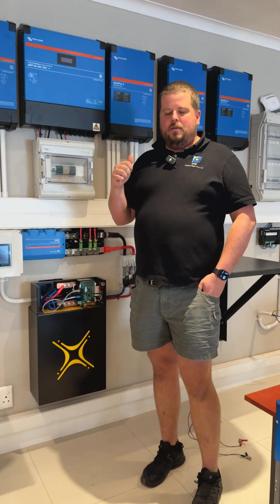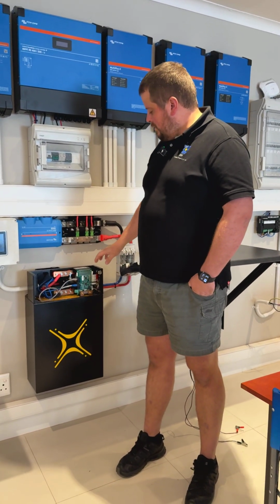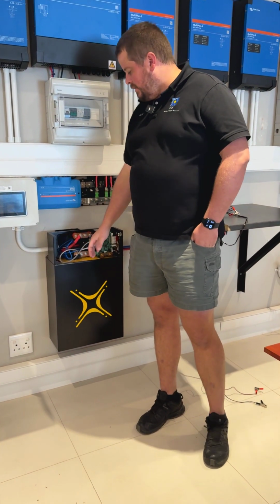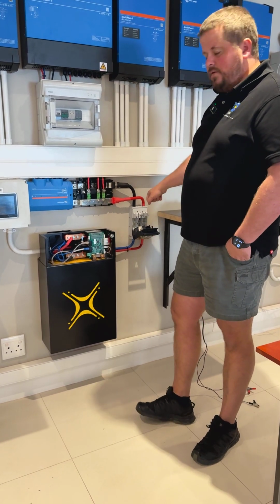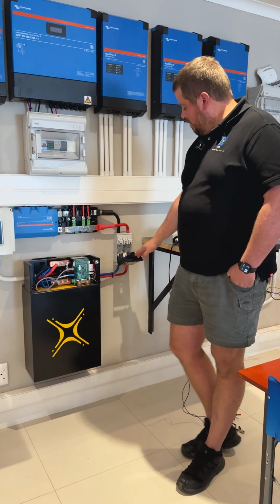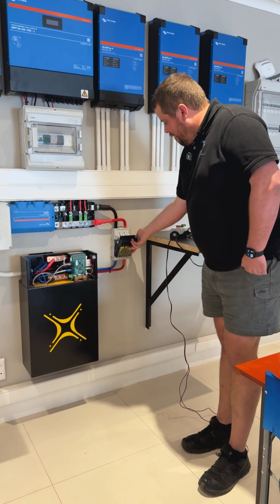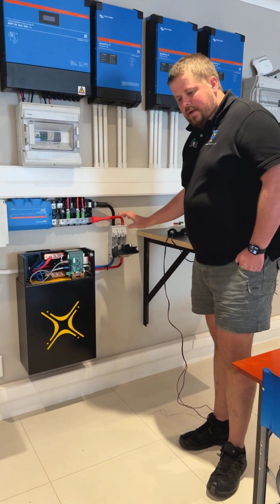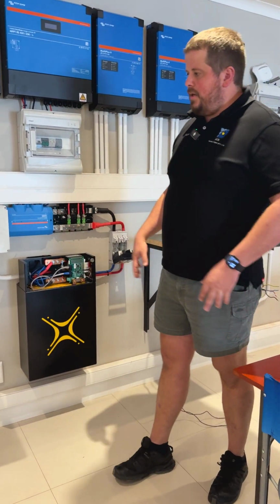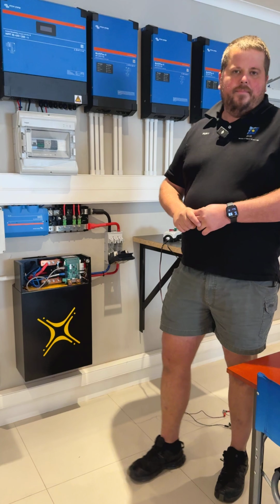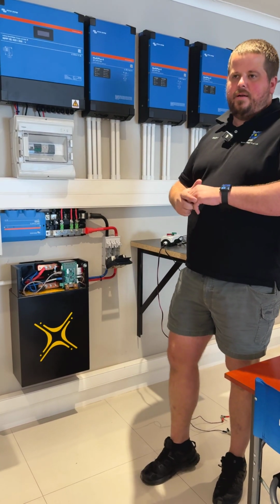Secondly guys, you damage batteries by just switching on the battery and closing this fuse. This is your pull fuse. There are multiple names for it: fuse disconnector, battery disconnect, in case of emergency disconnect.